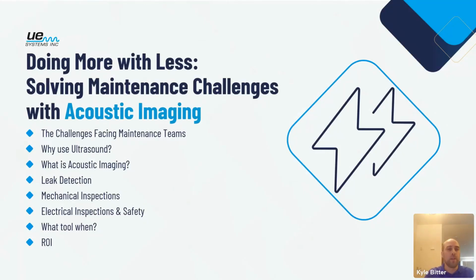You have the ability to point out those bad apples and then take further action - maybe pairing an acoustic imaging camera with an Ultra Probe 15,000, one of our handheld Ultra Probes, to do further inspections, capture sound files, and perform precision lubrication, maybe with the Ultra Probe or the 401 grease caddy. We'll touch base on that as well.